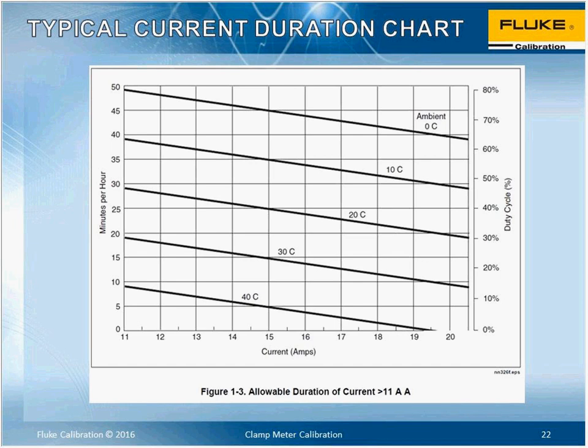So unless you're automating your procedure, it might be difficult to get a measurement within that period before you run into spec issues. Also, there's typically a cool down period, so this is all cumulative. If I ran it for 5 minutes at 11 amps, then ran it for another 10 minutes without letting it cool down, I actually have a cumulative effect where it seems like I've run it for 15 minutes, because it's thermal based. It didn't have a chance to cool down.